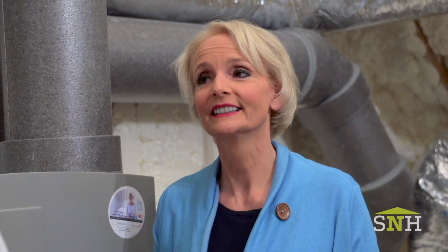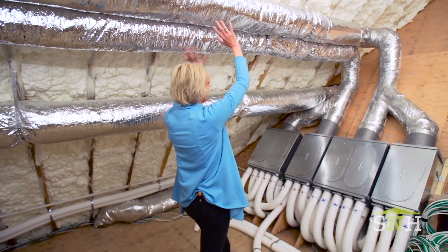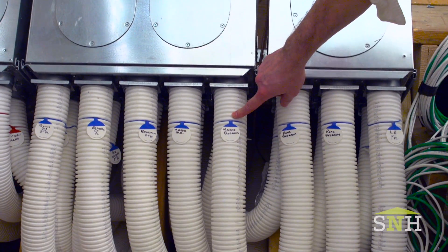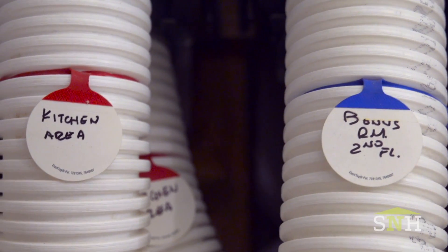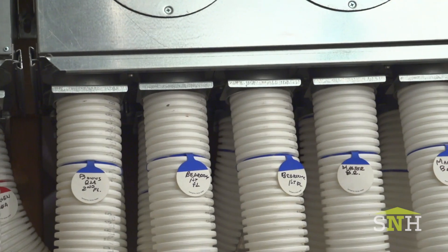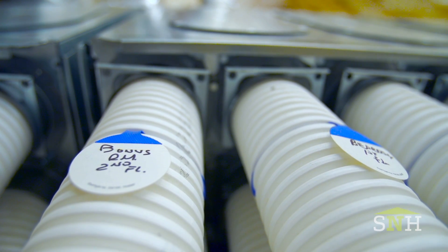That's really big. Very big. As I follow these shiny insulated lines right over here, it takes me to some distribution boxes. The air stream is divided into silencers, then sent through these manifolds and tubes through the rooms where CO2 levels increase — typically bedrooms at night with doors closed. To enhance sleep, we often supply fresh air to bedrooms so people get a better night's sleep. This was the most time-consumptive element of the entire installation. It's beautifully labeled now — red and blue. The red tubes are returns and the blue tubes are supplies, going to bathrooms and bedrooms depending on whether it's supply or return.